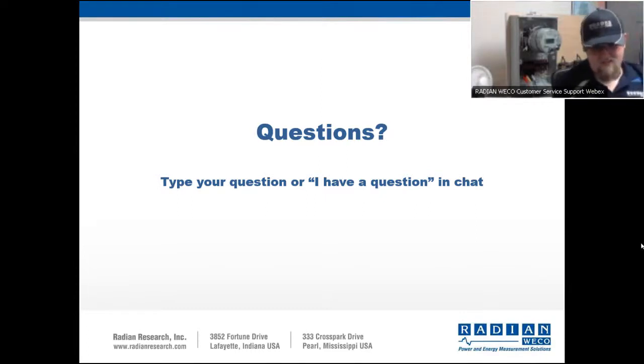Another question I saw is, can you move the CT probe without waiting after you hear the beep on the RW? Preferably not. You can, but you won't get good results. The reason is that the beep occurs when the test is done. If you move it before, you're killing the primary reading during the reading process of the RW. You're going to probably ruin part of the end of the burden test, so you'll see some real high error. When it does beep, that's when you can go ahead and move it. You know that the RW's done its measurements, you're good, you can move it over that way.